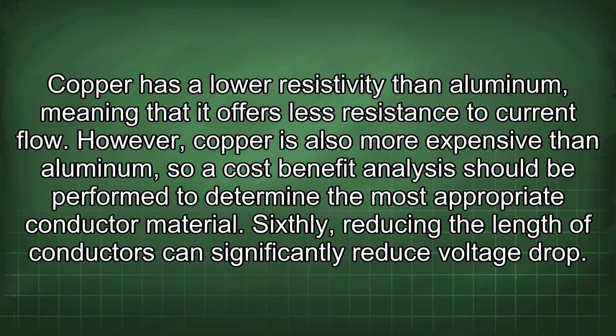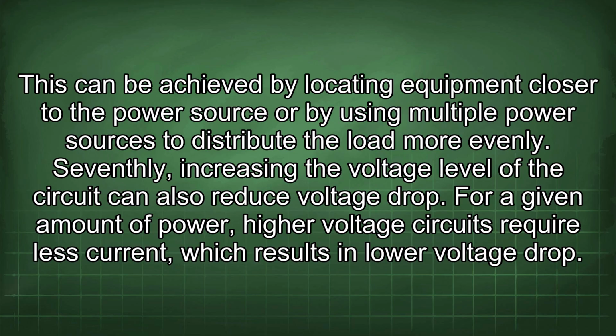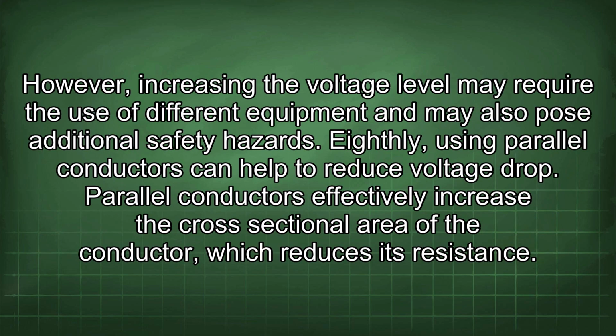Sixthly, reducing the length of conductors can significantly reduce voltage drop. This can be achieved by locating equipment closer to the power source or by using multiple power sources to distribute the load more evenly. Seventhly, increasing the voltage level of the circuit can also reduce voltage drop. For a given amount of power, higher voltage circuits require less current, which results in lower voltage drop. However, increasing the voltage level may require the use of different equipment and may also pose additional safety hazards.